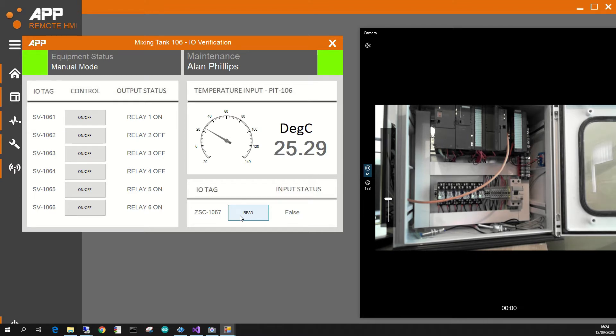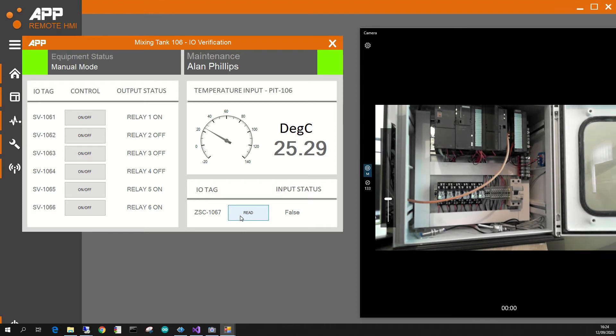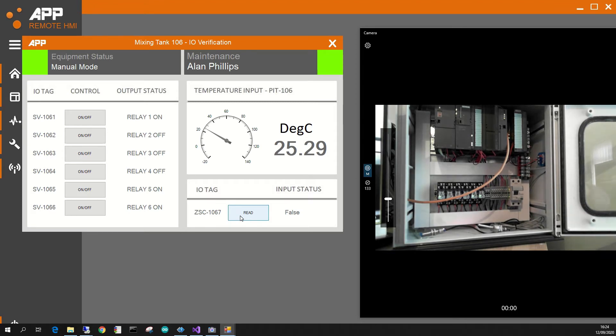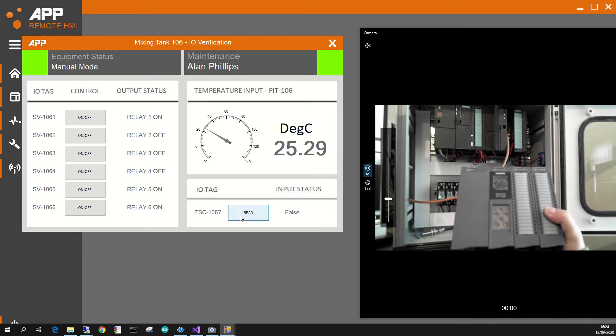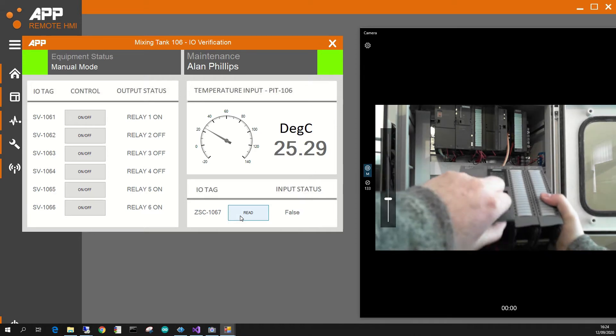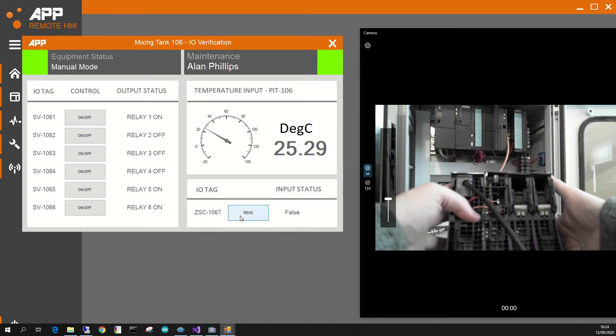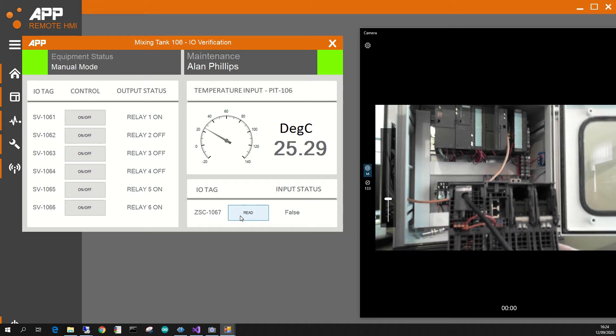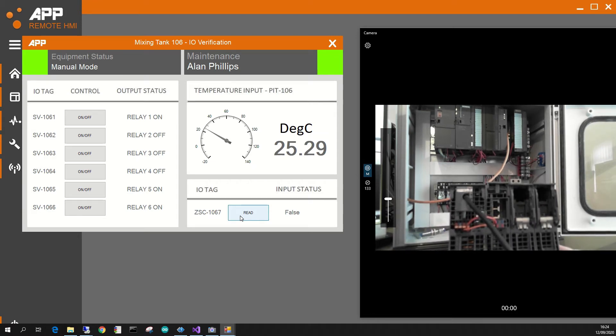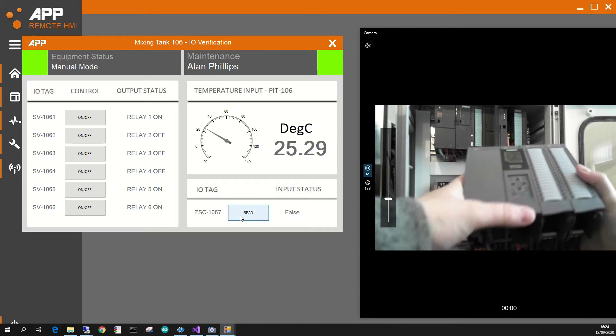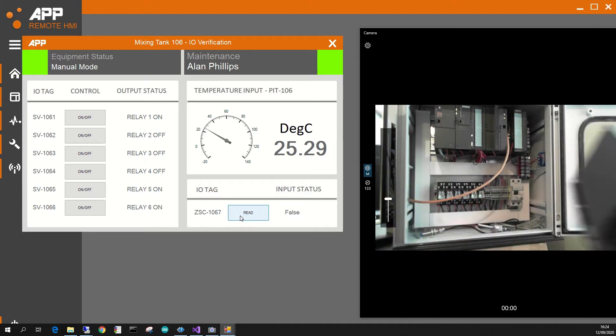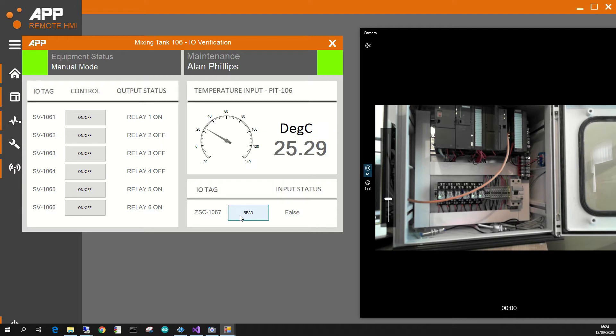So again, just to cover it a second time, you need to have an ethernet card or you need to have a CPU that actually has an ethernet card such as, say for example, this is a 1500 and in the 1500 you're going to see that there's effectively two ports there. So you can have two different RJ45 connectors go in and read directly from the CPU. If you don't have that, then you won't be able to use the library in the same way.